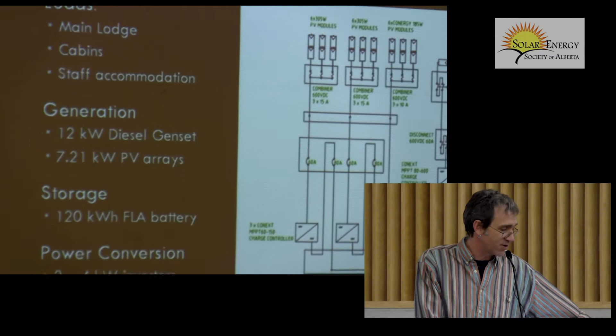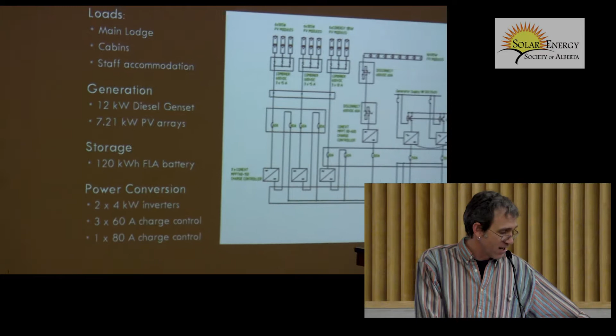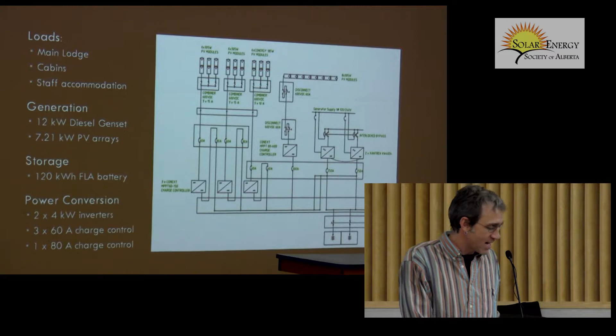We've got about 120 kilowatt hours of flooded lead acid batteries, 2 4-kilowatt inverters, and as I mentioned, 3 60 amp 150 volt charge controllers and 1 80 amp 600 volt charge controller.